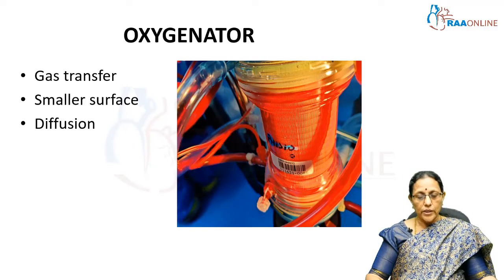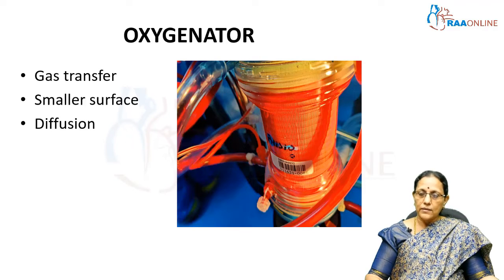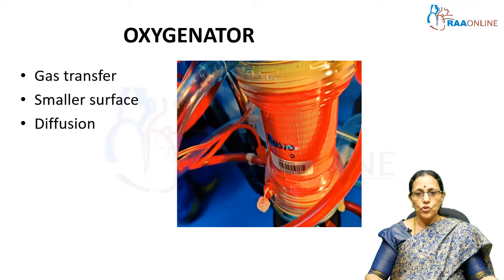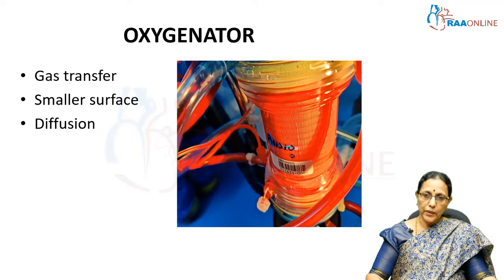The oxygenator should have a smaller surface area, and at the same time it should oxygenate the blood in a very efficient way. In a membrane oxygenator, there is a trans-membrane which separates the blood and the gas, and gas exchange takes place by diffusion, so the diffusion efficiency should be very good. In a bubble oxygenator there is direct interface of gas and blood, and diffusion in a bubble oxygenator should likewise be very efficient. Such are the criteria on which an oxygenator has to be manufactured.